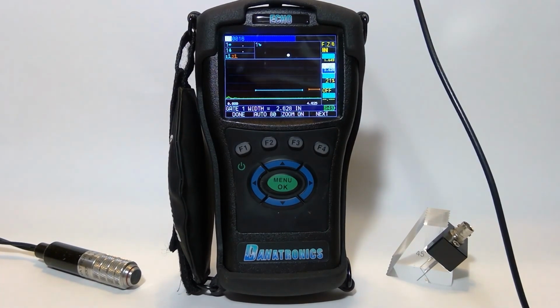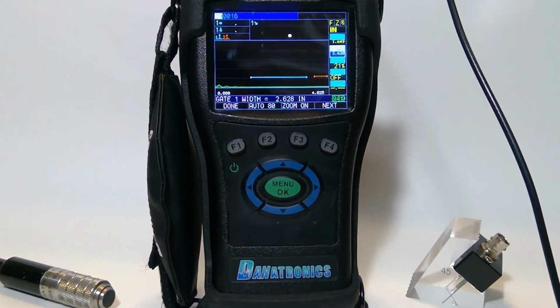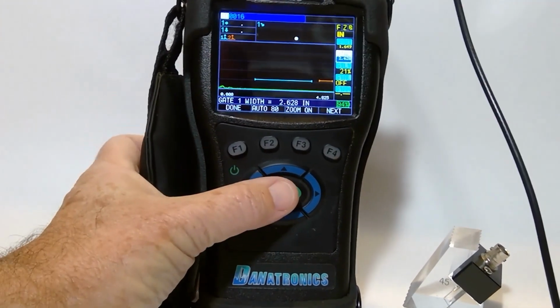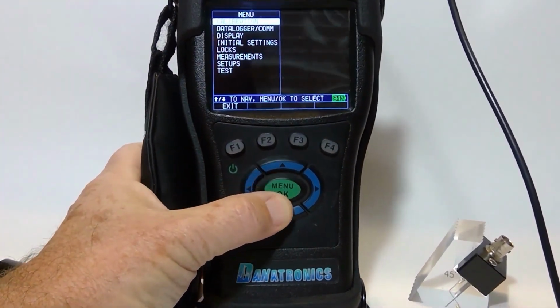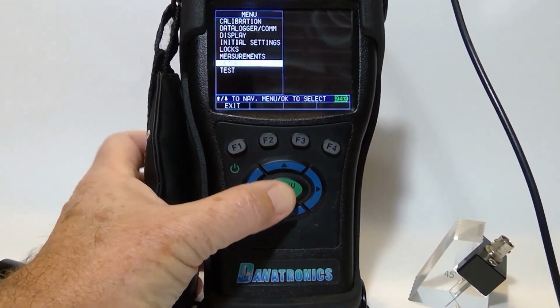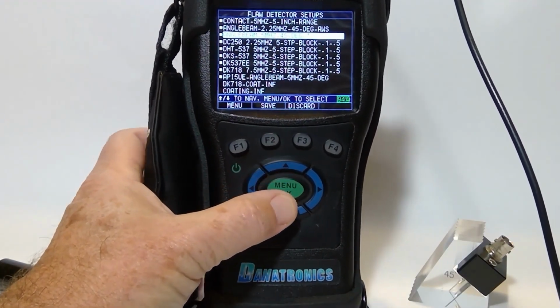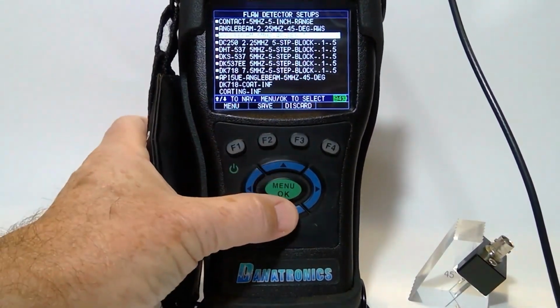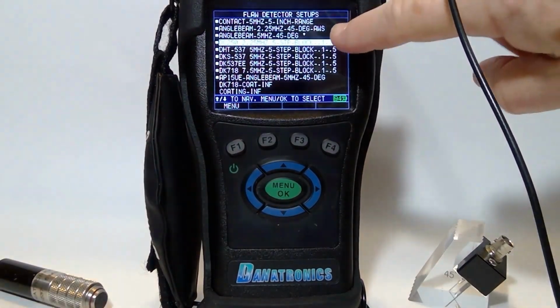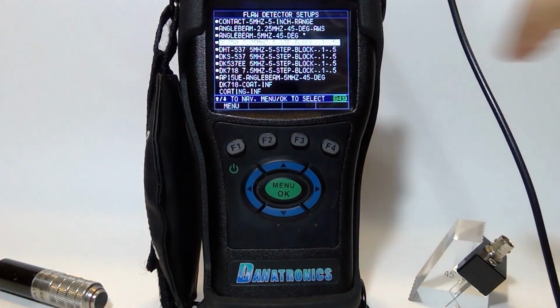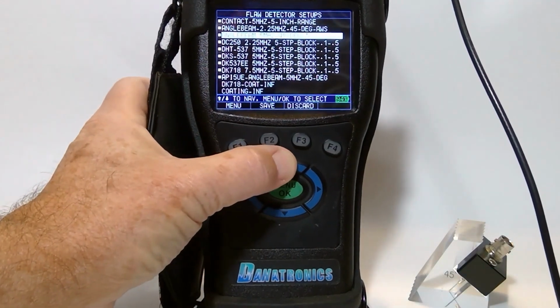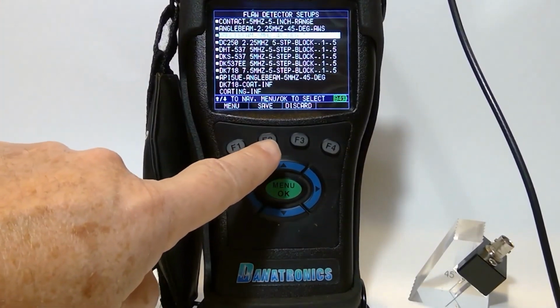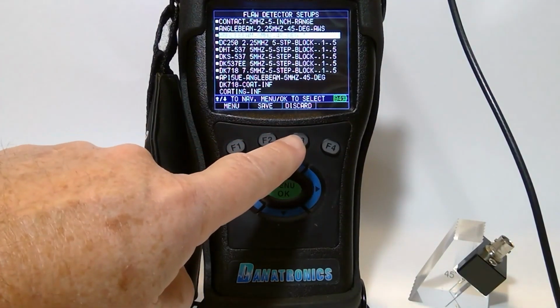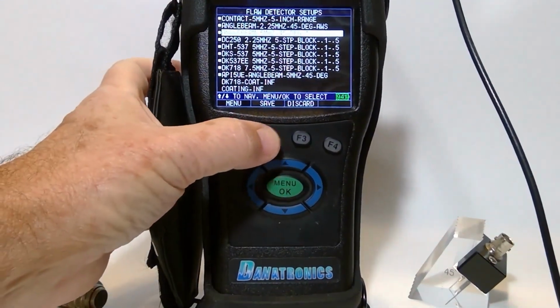Now that we've calibrated, let's go ahead and store that calibration in the gauge under Setups. Zoom in a little bit. I press OK. Slide down to Setups. Hit Enter. If you'll notice, the setup that I was just using has a small asterisk beside it. That means that I have changed that setup. So I highlight it. And if you'll notice at the bottom, I can either save or discard that setup.